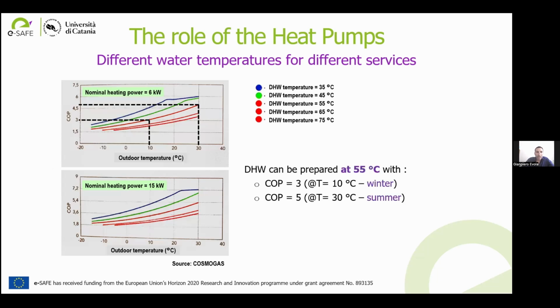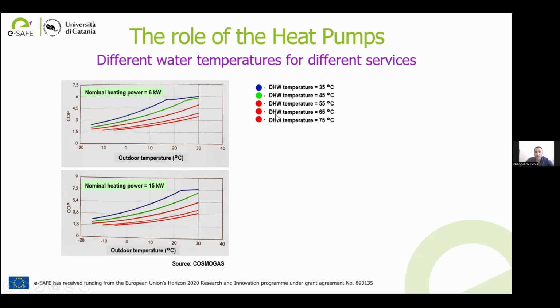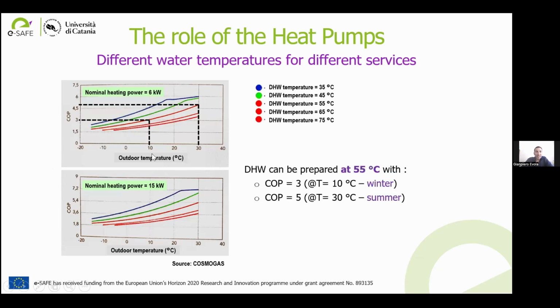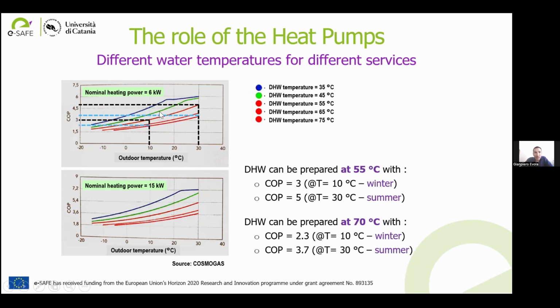For instance, in these plots, we can see the COP of several units at several domestic hot water temperatures. In the summer, when the outdoor temperature is 30 degrees, with the 55 degrees hot side, we have a COP around 5, but this becomes 3.7 when the hot water temperature is around 70 degrees. In the winter, at 10 degrees outdoor temperature, we have normally a COP around 3, but if we want to work with higher domestic hot water temperatures, the COP becomes 2.3. So we lose around 30% efficiency if we want to work with very high temperatures. But this is still possible, which would not be possible with common heat pumps.